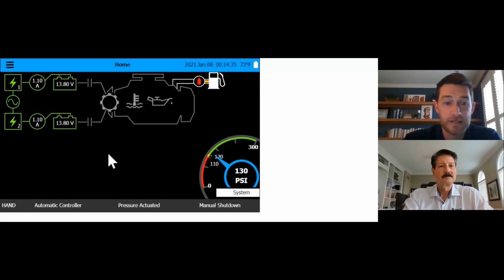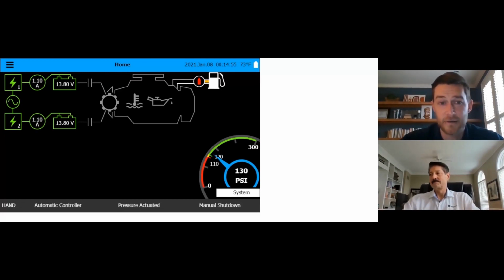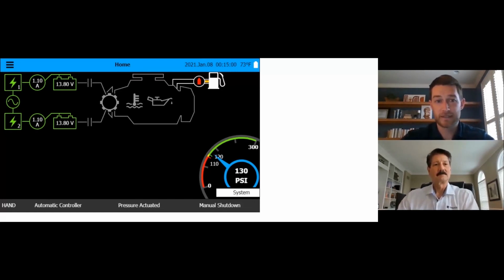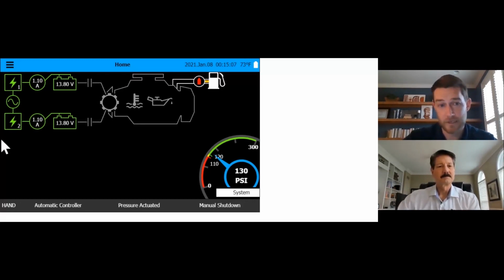So continuing on to the right, you have the same parallel lines right there, showing that those contacts are open. Those are the start contacts for the motor. And then you've got the gear, which is the starter itself. It's going to show when we're trying to start, because when you're trying to start the engine, it's going to give it 6 tries in an automatic start. So you're going to pull from one battery bank, and you'll see the contacts close at the top for that one. And then if it's not successful on the first try, it'll switch over to the second battery bank, and you'll see the contacts closing down on the bottom.